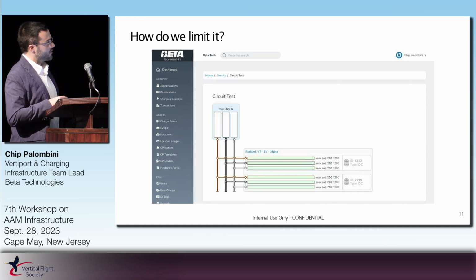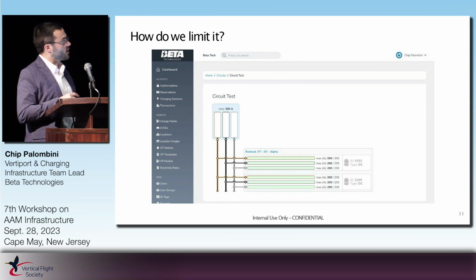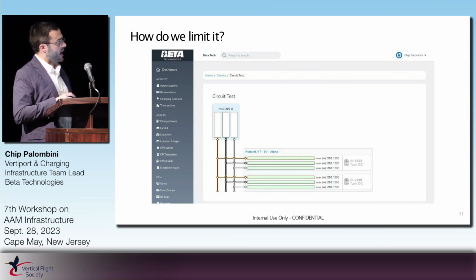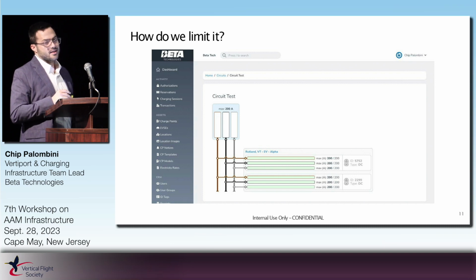Getting back to the demand charge, we do have a method where we can manage peak demand at a single site. In this example it's a nice graphical interface. We can say the max at this site is 200 amps. This is Rutland, Vermont, we have 2 chargers here, each one capable of 200 amps. Our system will monitor the instantaneous power at each of these and limit one, so that the aggregate demand does not exceed 200 amps.